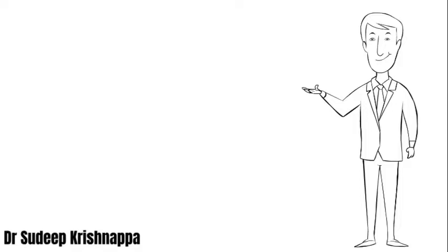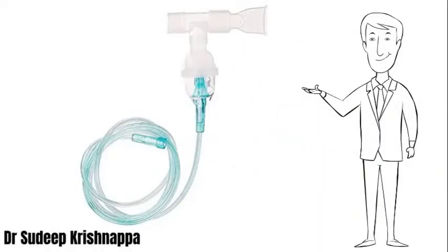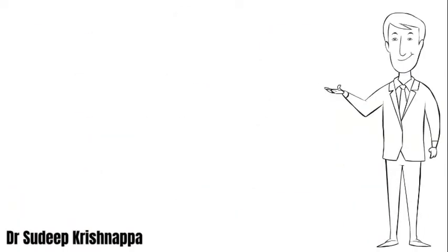These nebulizers come in various shapes and sizes according to the manufacturer's specifications; however, all of them have the same basic components. We have a tubing, one end of which is connected to a compressed air machine or oxygen flow, and the other end is connected to the nebulizing chamber, which in turn is connected to either a mask, mouthpiece, reservoir bag, or a T-piece to facilitate delivery of the nebulized solution into a ventilatory circuit.